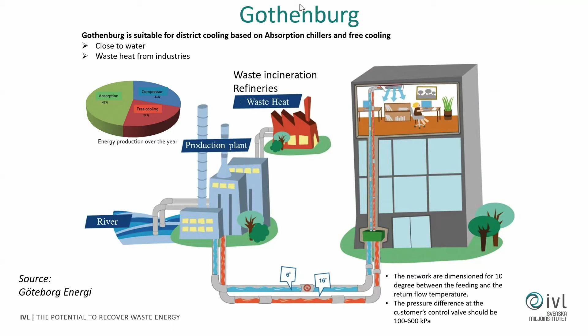The networks are dimensioned for a 10-degree difference between the feeding and return flow temperature, with pressures at the customer control valve in the range of 100 to 600 kilopascals.